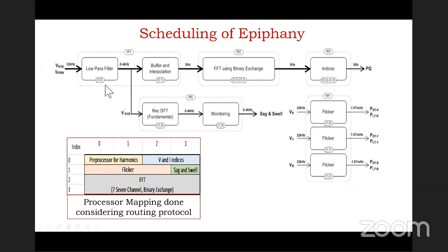So I need only 6.4 kilohertz. We take the 6.4 kilohertz, buffer it, and send it to the binary exchange platform, and then get the indices of PQ indices at different intervals. So if I'm sampling at 64 kilohertz, that doesn't mean I'm giving all the output at that rate. The output comes at 5 hertz. That's the meaning of that.